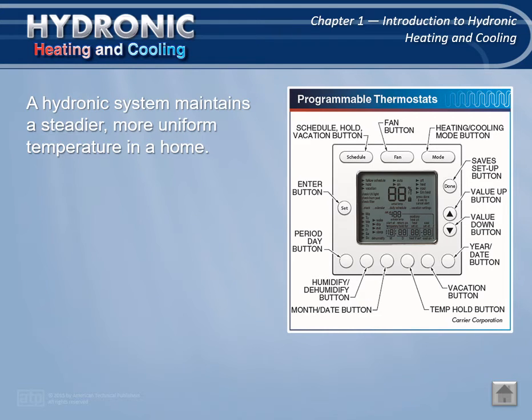For best comfort, a heating system must keep body heat loss within the correct proportions using radiation, convection, and conduction. Since the greatest amount of body heat is lost by radiation, it is logical that the system that most satisfactorily controls this loss is best able to create a comfort condition. Hydronic heating does exactly this because the thermal units most effectively warm a space's interior surfaces. The temperature of the supplied heat transfer fluid from the boiler is sometimes controlled automatically according to the outside temperature using a master sub-master control system.